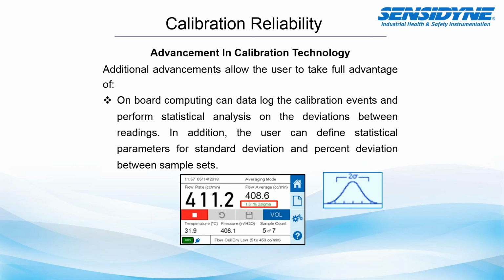So if you are showing a high 2 sigma, that means that your sample set is all over the place, that there's pulsation going on. This usually shows that there's some sort of yawing or bias of your pump itself. Your pump could have a poor stability in and of itself, or there could be bias introduced by those other factors, being the sample train or the calibrator. But it's important that if you want to record a stable flow set, that you have a really tight standard deviation.